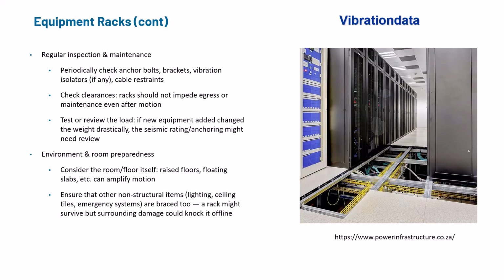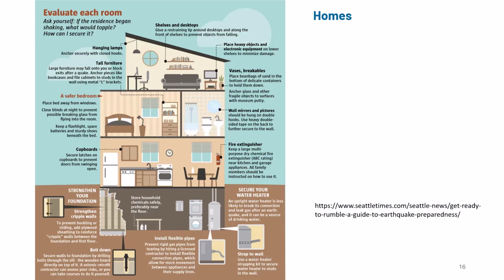As mentioned, the room itself—raised floors, floating slabs—can amplify motion, and we don't want that, but it does happen. Even things like lighting, ceiling tiles, and sprinkler lines, heaven forbid there's a fire, all need their own type of bracing as well. So a rack might survive, but surrounding damage from these other components may knock it offline, which is bad news.